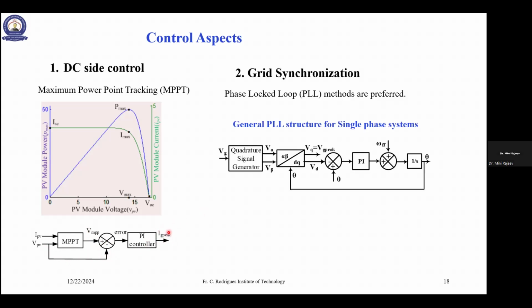So that is one DC side control. Next is grid synchronization. When you generate from an inverter, your voltage and frequency should match the grid voltage and frequency. Depending upon active and reactive power, there will be a small difference in phase angle or magnitude, but otherwise it should match. If you're transferring active power, your magnitude should match, your frequency should match. Otherwise, there will be circulating currents.